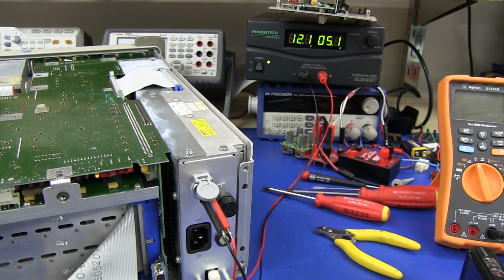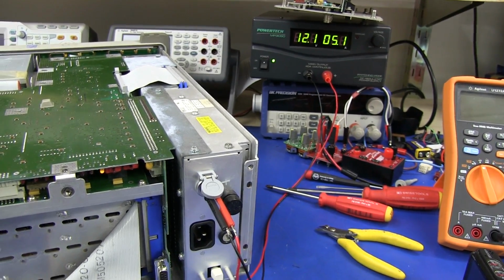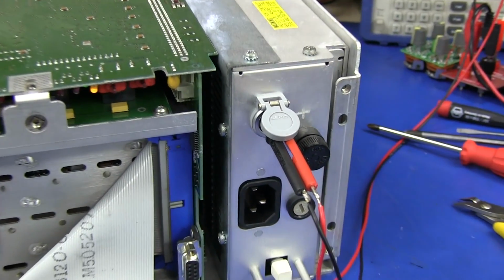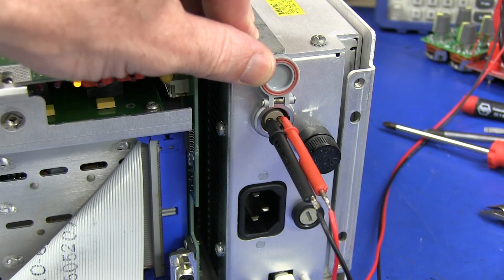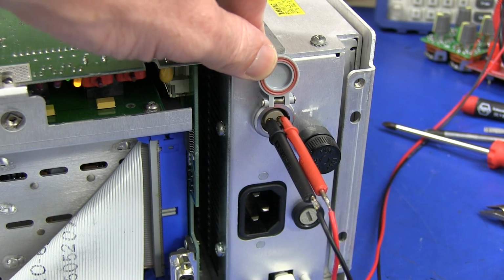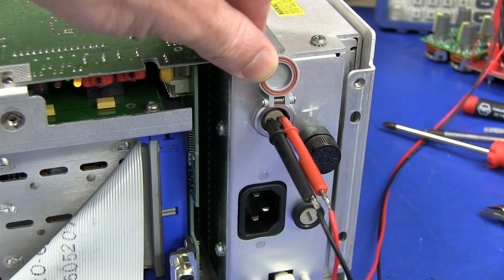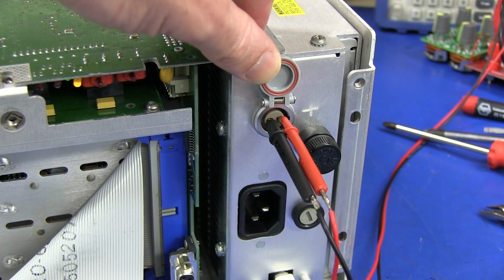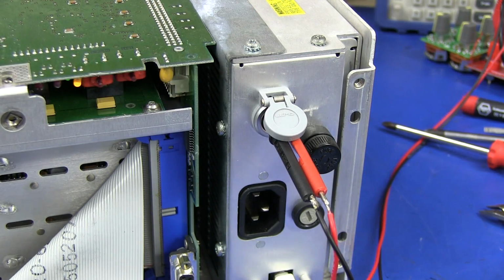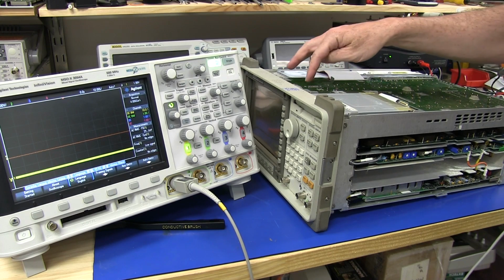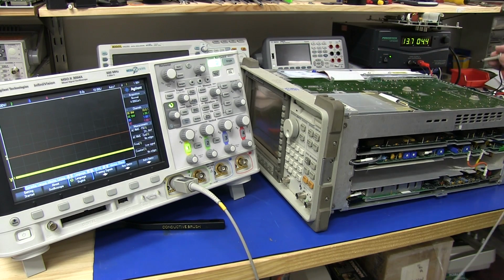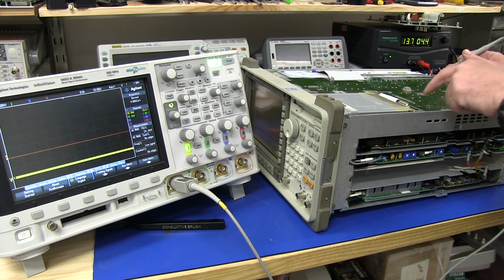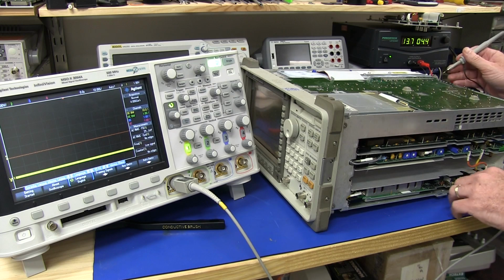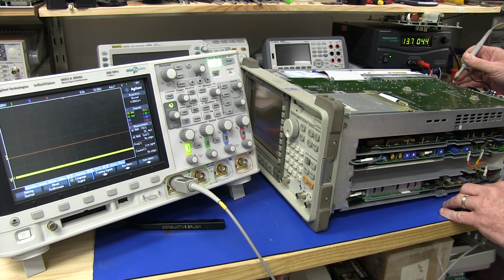External 12 volt DC power at about 5 amps. That gives us about 60 odd watts power consumption for this thing. And that 2-pin LEMO connector in there, I'm not sure exactly the type, but the contacts in there seem to precisely take a standard 2mm test probe pin. So, hey, hacked up some old probes and we're good to go. There are actually some test points on the back of these. They're single inline headers here, and although they're not marked on the silk screen on the bottom, because there is no silk on the bottom, which is really rather annoying, you can get the reference from the service manual.